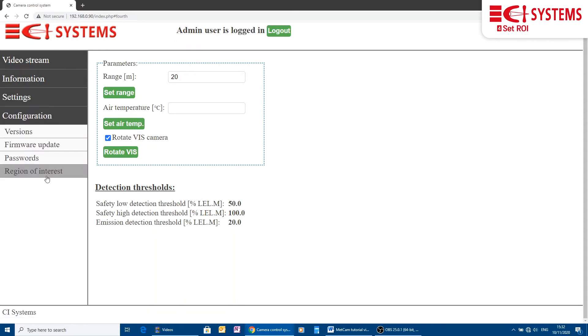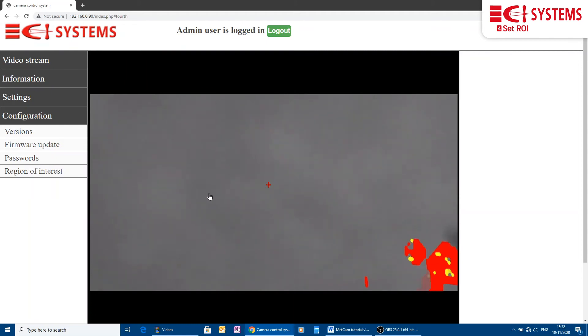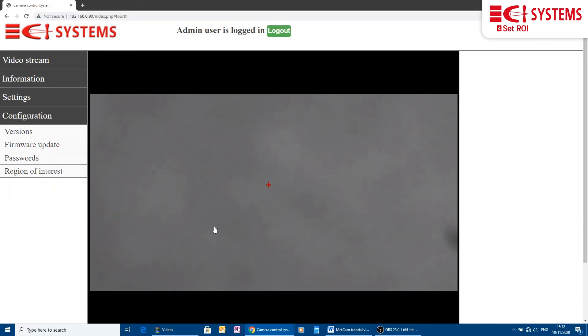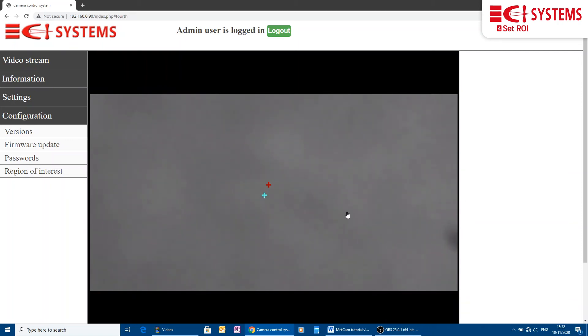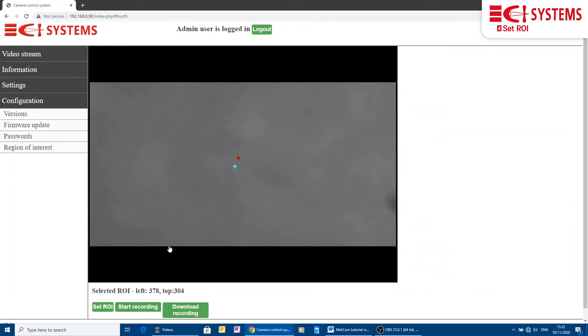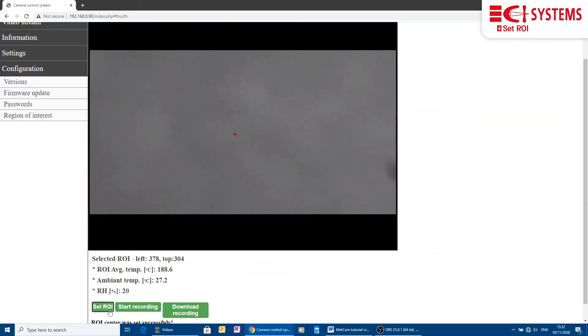We proceed to mark the region of interest. The marker is used to track the ambient temperature of the scene, which is used to decide on system inhibition. We click on the image to move a white cross. Once we are happy with the location, we press the set ROI button and the white cross turns red. It is advisable to select a man-made object close to the main monitored area.